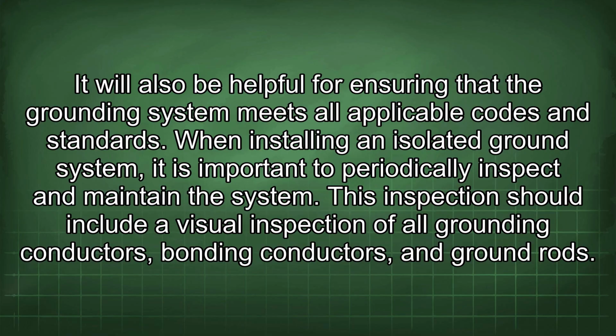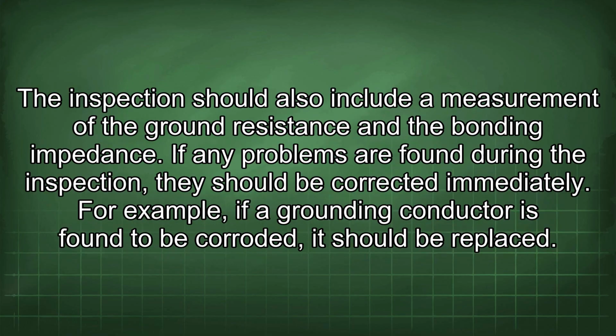When installing an isolated ground system, it is important to periodically inspect and maintain the system. This inspection should include a visual inspection of all grounding conductors, bonding conductors, and ground rods. The inspection should also include a measurement of the ground resistance and the bonding impedance. If any problems are found during the inspection, they should be corrected immediately.